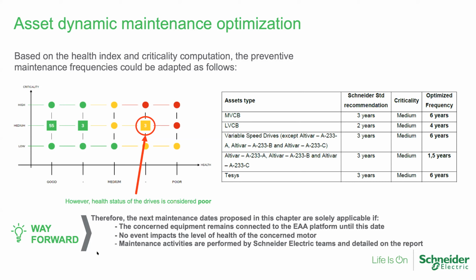When we have continuous 24/7 monitoring and people analyzing the behavior of the electrical assets, after establishing a baseline of operation we can start making dynamic maintenance recommendations—shifting from the expected traditional schedule-based maintenance, which might be every three years or annually depending on each company's philosophy. We can then say, based on the utilization of your assets, the electrical stress, and other factors we monitor, and foreseeing continued similar usage against that baseline...